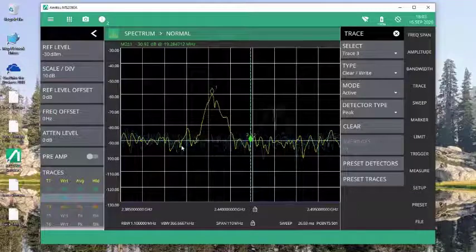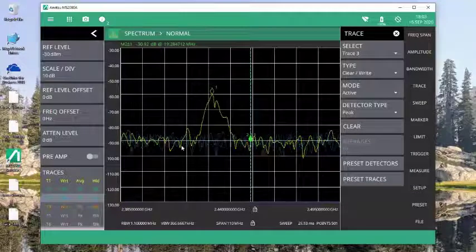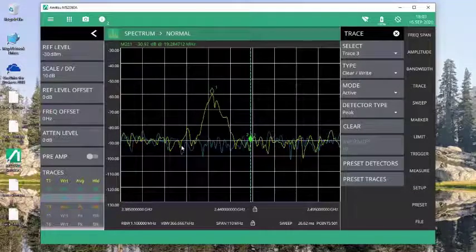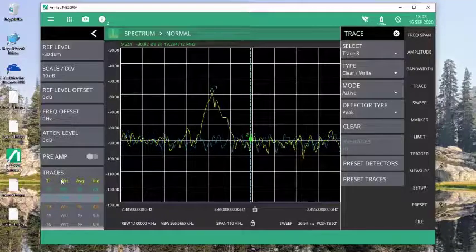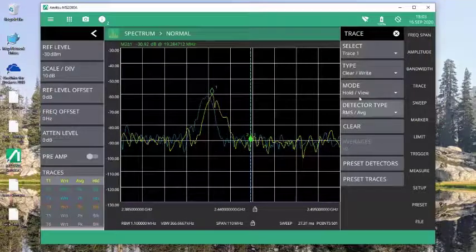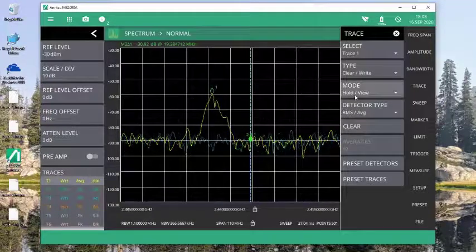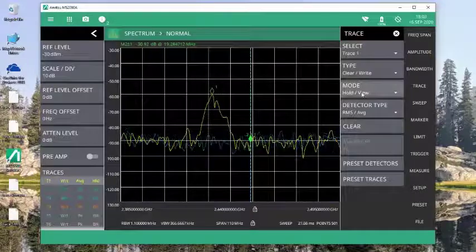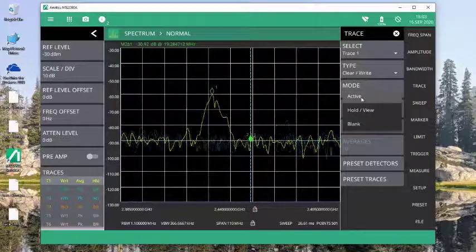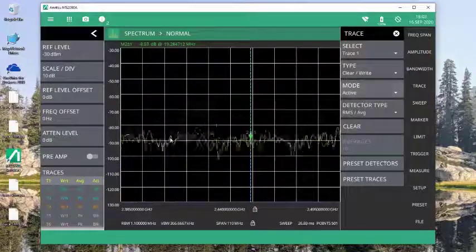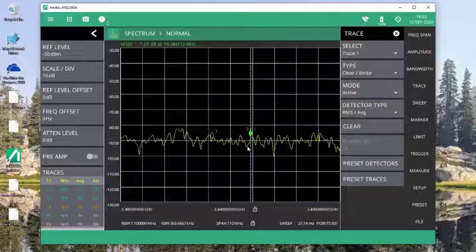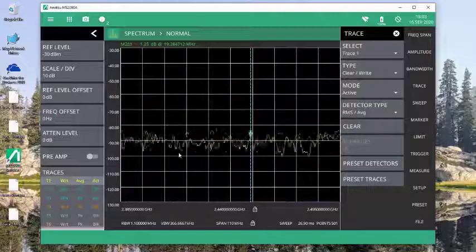Now if I want to go back to have trace 1 taking live measurements, I simply go back to my trace 1 settings. You'll see here that it's recalled into a hold view mode. I change that back to active, and now both traces are actively sweeping.